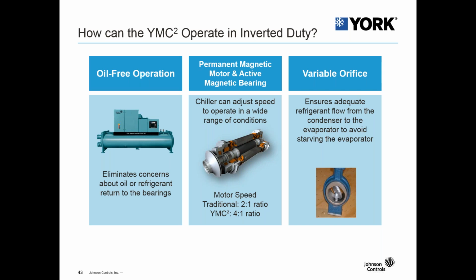We also have the permanent magnet motor, and the advantage of the PM motor is the chiller is able to adjust the speed to operate across that wide range of conditions. On a traditional motor, you would have a turn down of a 2-to-1 ratio. However, with the speeds that we're operating on the permanent magnet motor, we have much more turn down, a 4-to-1 turn down ratio.